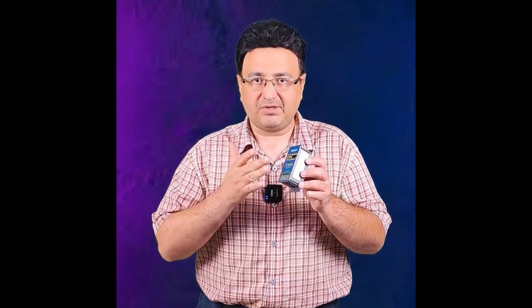Hello and greetings. Today we want to get more familiar with the load cell transmitter. A load cell transmitter is a device to which we connect the load cell, and it gives us a standard analog signal. This standard analog signal can be either 4 to 20 milliamps or 0 to 10 volts. This device has many applications in industry, including the ability to connect the load cell transmitter to a PLC or, for example, to send a command to a drive.